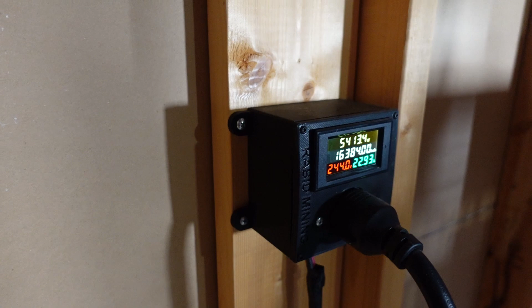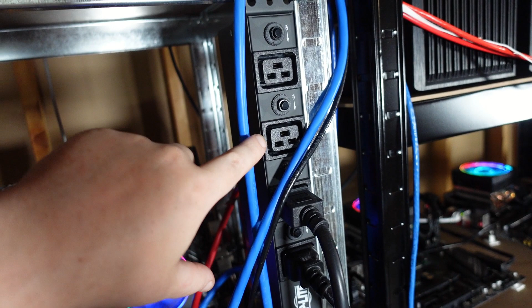The whole PDU is set for 30 amps, up to about 300 or 400 volts. This one I'm running at 240. Each outlet here is on its own separate individual button, little mini breakers within it like a reset button, and they're at 12 amps each.